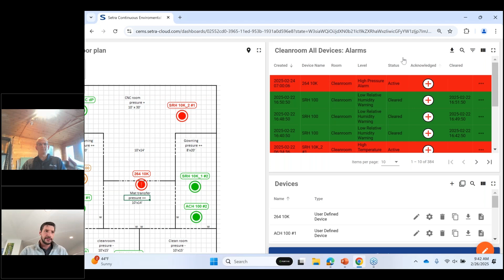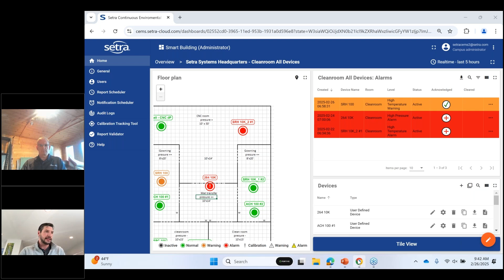I can see that alarm acknowledgement, this one now has a check mark saying that alarm was just acknowledged by me. And I can go over to my audit logs and see that alarm acknowledgement here, so all that is captured. If you ever do get audited, you can export your alarm table as well as your audit log table, and it'll show exactly what you did to get your system back within compliance.